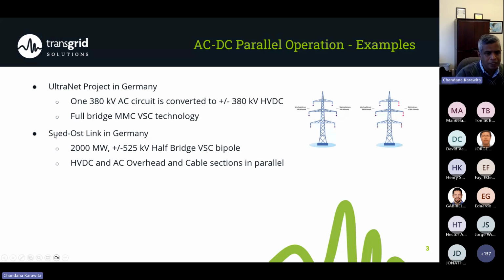And then the next one that we got involved in was the Süd-Ost link in Germany. And again, here they are sharing the right of way. Actually, this is a 2000 megawatt plus minus 525 kV half bridge VSC bipole. If you're familiar with the rigid bipole configuration, this is a rigid bipole. That means there is no DMR or electrode, and it's positive pole and negative pole operating in symmetrical mode all the time.